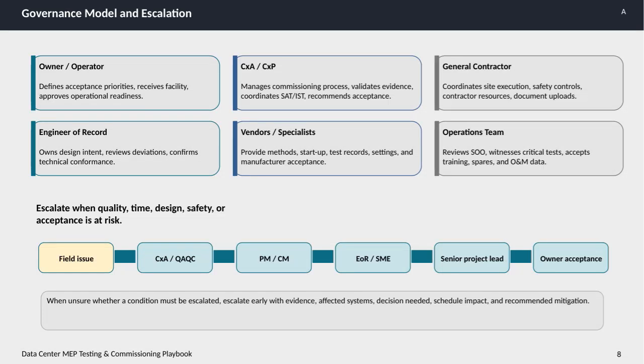On this slide, we're looking at the governance model and escalation process for data center MEP testing and commissioning. First, the owner or operator is responsible for setting acceptance priorities, taking delivery of the facility, and approving operational readiness. They ultimately decide when the project is ready to go live. Next, the commissioning authority or provider, or CxA/CxP, manages the commissioning process.